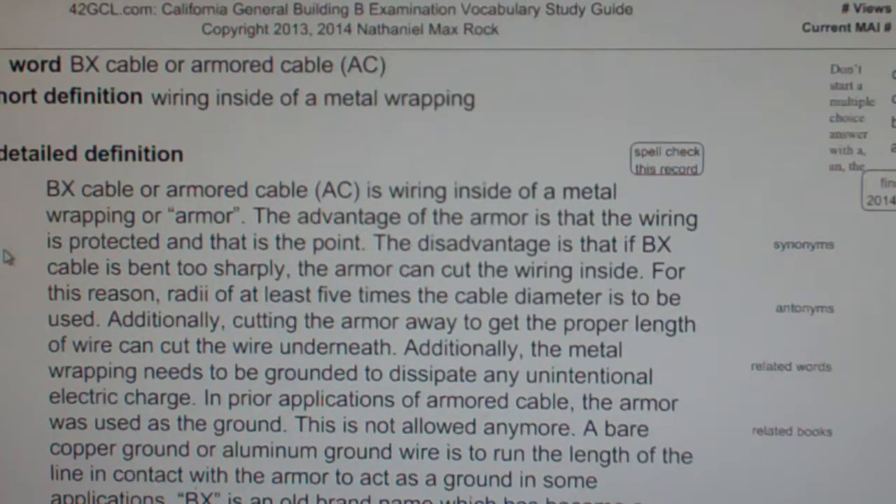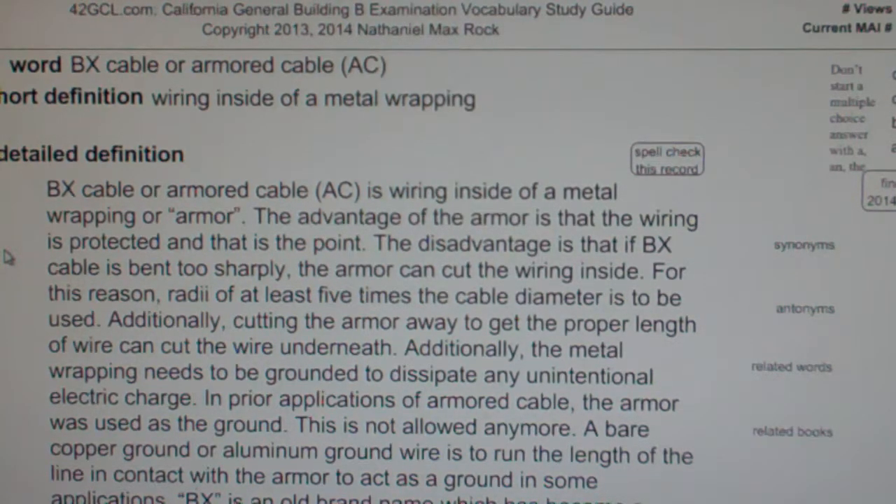The metal wrapping needs to be grounded to dissipate any unintentional electric charge. In prior applications of armored cable, the armor was used as the ground. This is not allowed anymore. A bare copper ground or aluminum ground wire is to run the length of the line in contact with the armor to act as a ground in some applications.